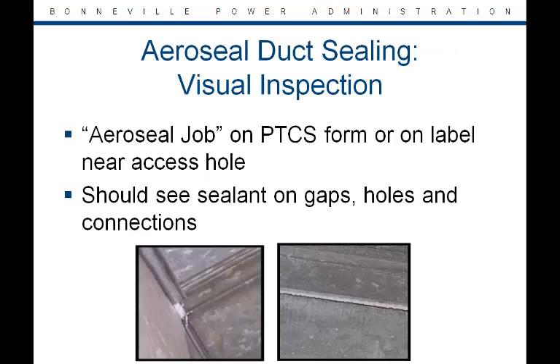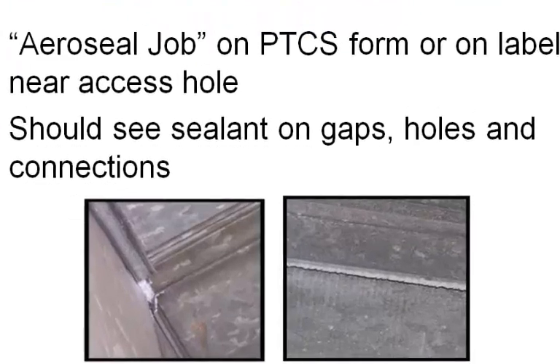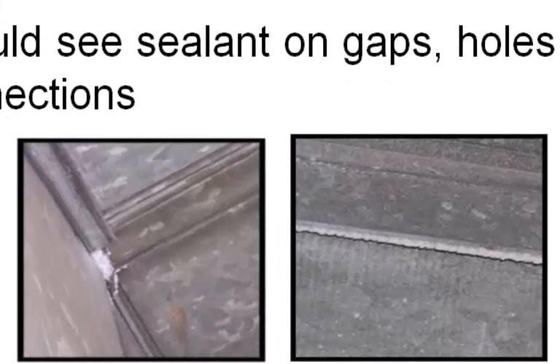A visual inspection of a home sealed with AeroSeal, an AeroSeal sealant applied from the inside of the ducts with special equipment, is a little different. It may be indicated on the form or label near the access hole that the system was sealed with AeroSeal. Such a duct system will have sealant in the gaps, holes, and connections as illustrated in these photos. AeroSeal is an acceptable mastic substitute, but it does not eliminate the need for mechanical fasteners, duct tape removal, or any other PTCS specification.